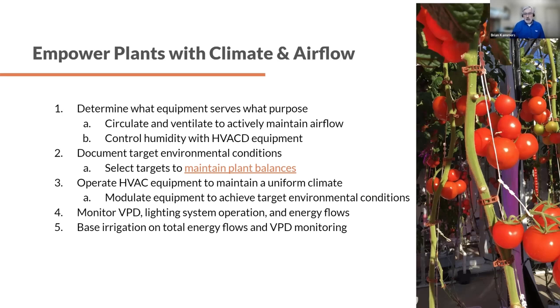Now, a lot of growers will have different set points depending upon the maturity of the plant. This is particularly true in cannabis, where they might have a certain VPD when the plants are little babies. And when they get bigger, you might have a higher VPD. And right before pre-harvest, you might drop the temperature to freak the plant out, think winter is coming. And you need to look at all those conditions to make sure your equipment can handle it. And if not, come up with either different targets or different equipment selection.